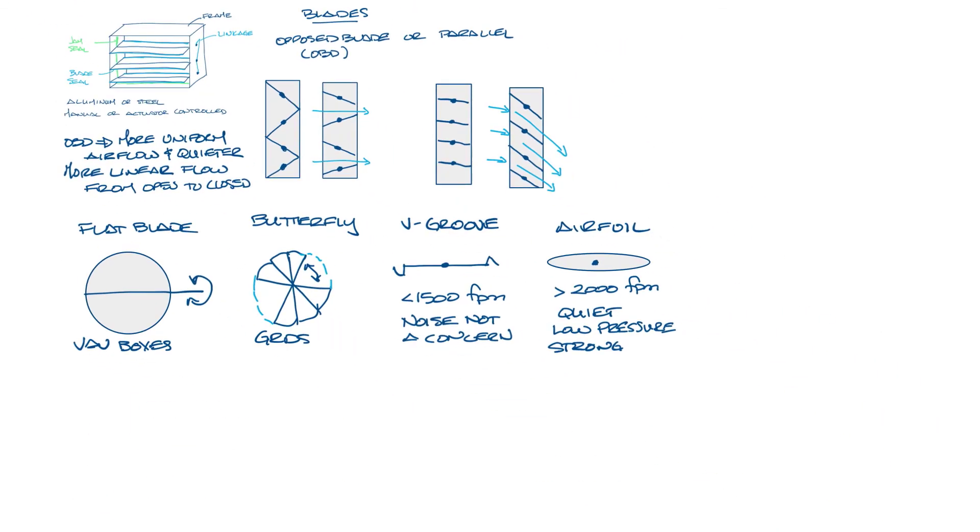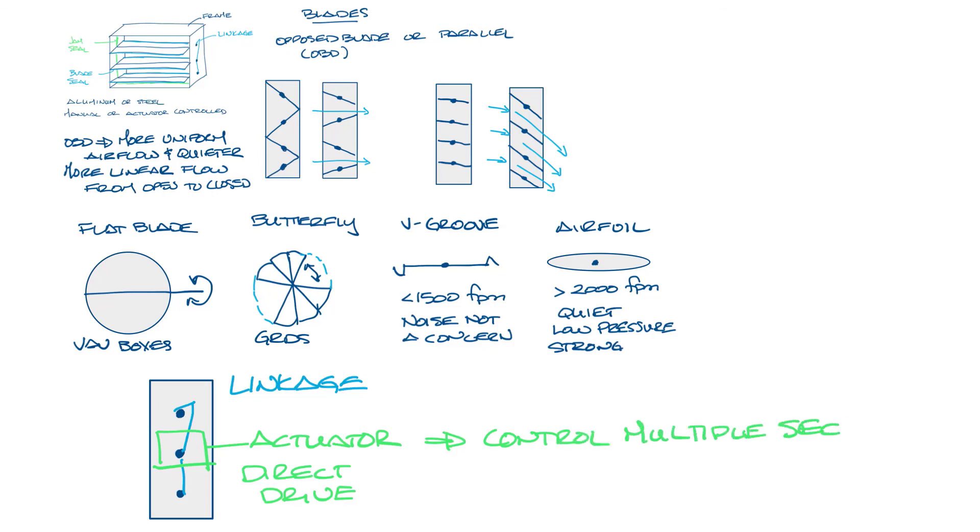The linkage connects the blades together. They are usually at the end of the blade and are driven by a single drive blade. If you mount your actuator here, it would be direct drive. A single actuator may power multiple sections of a damper or there may be one actuator per section. You can also get internally mounted actuators. Dampers can also be fitted with optional devices such as pressure sensors, smoke detectors, and position indicators.